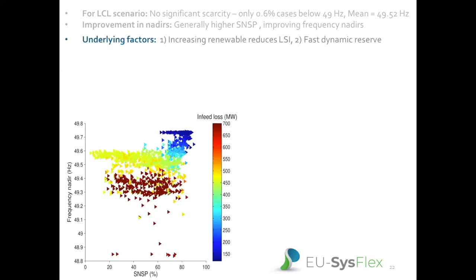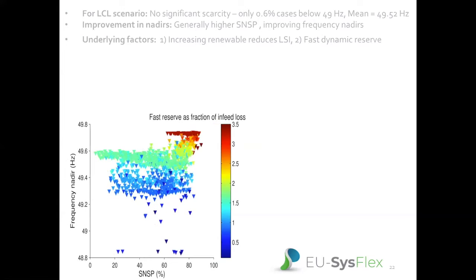Furthermore, fast dynamic reserves with a response time of hundreds of milliseconds, mainly batteries and HVDC interconnection, significantly impact the frequency nadirs, as can be seen in this figure. It is to be noted that the fast frequency reserve product currently deployed on the all-island system is modeled in these simulations, and it provides a significant amount of fast dynamic reserve.